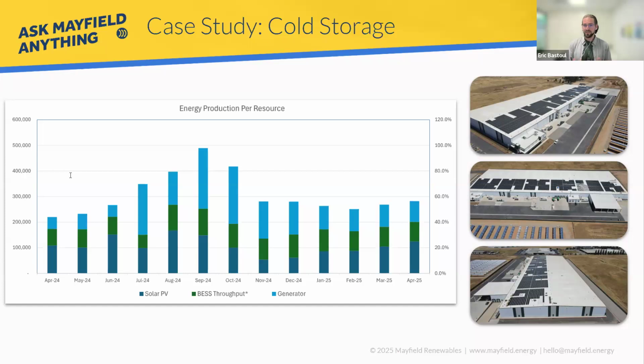Ultimately, what allowed this project to go forward was a microgrid made up of 1.2 megawatts of solar, 2.4 megawatt-hours of batteries with 1.2 megawatt inverter capacity, 2 1.2 megawatt natural gas generators to provide backup to the solar and batteries, and an average load of around 200 to 250 kilowatts throughout the day, giving an autonomy of approximately 18 hours.